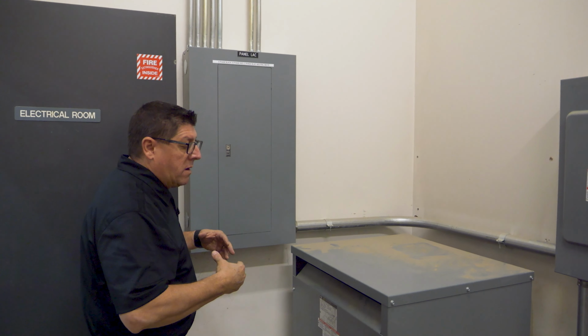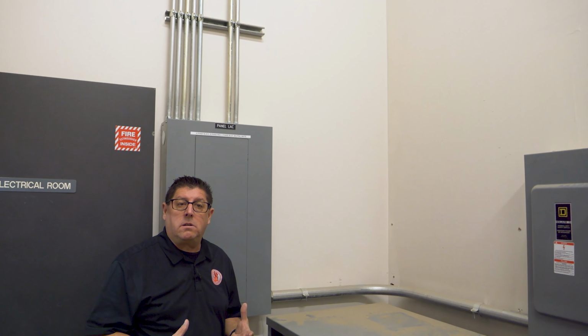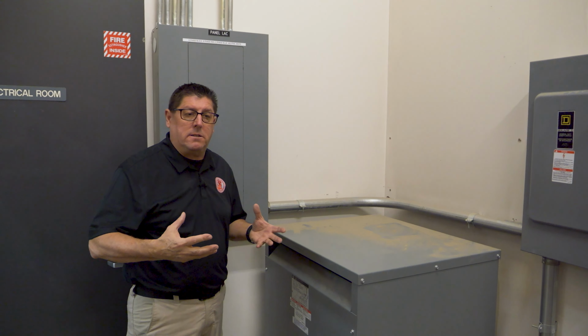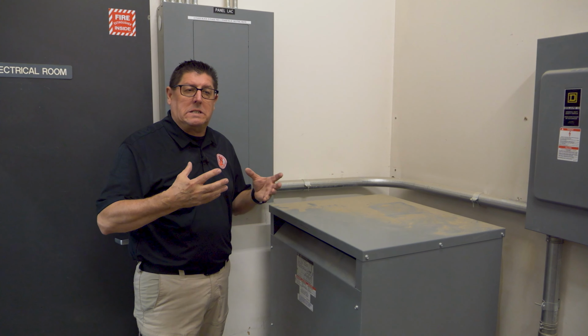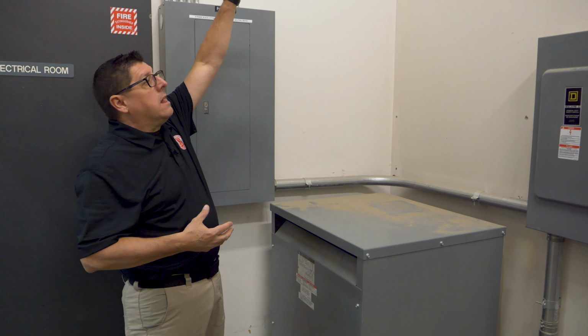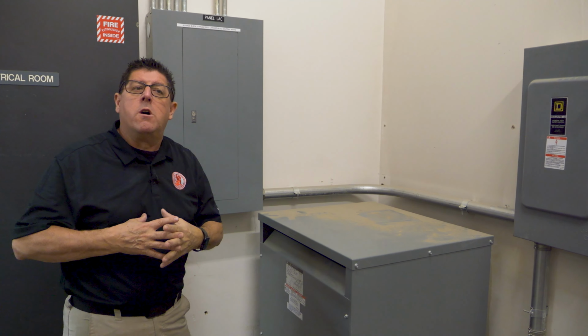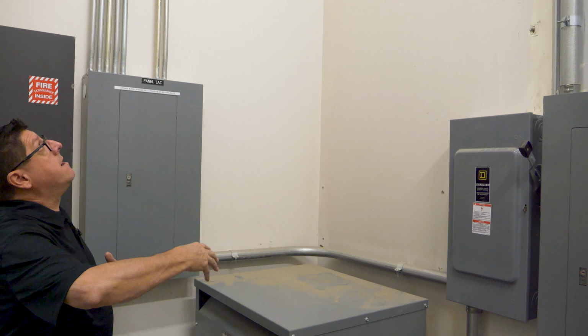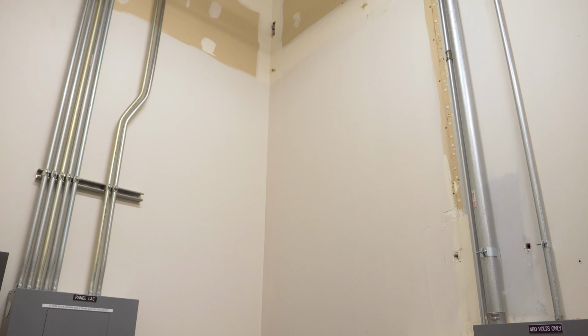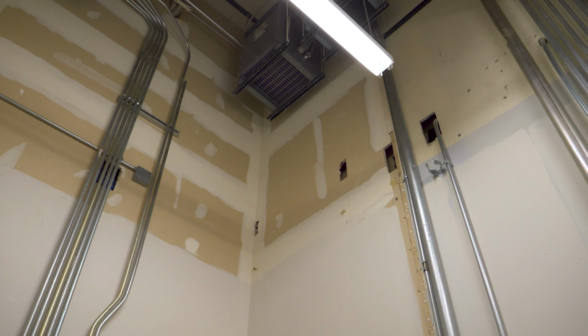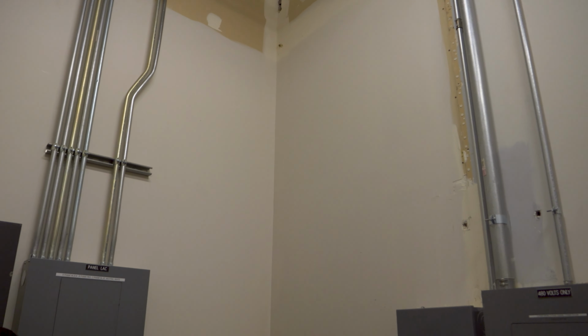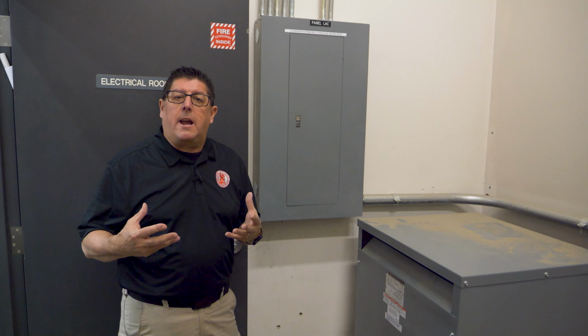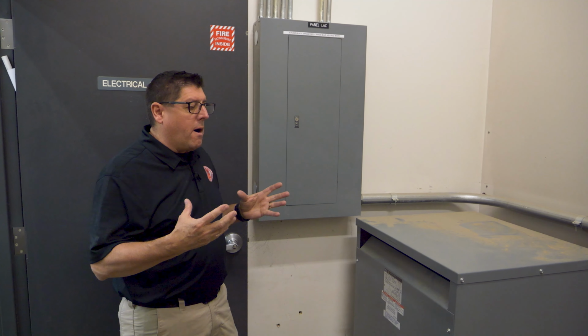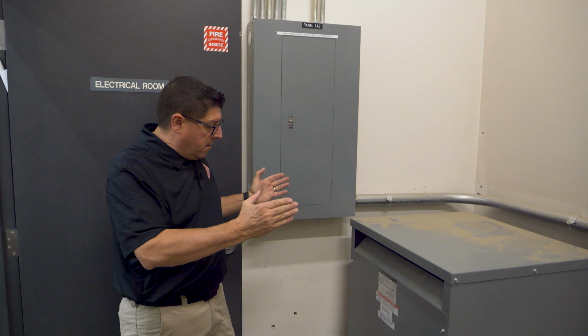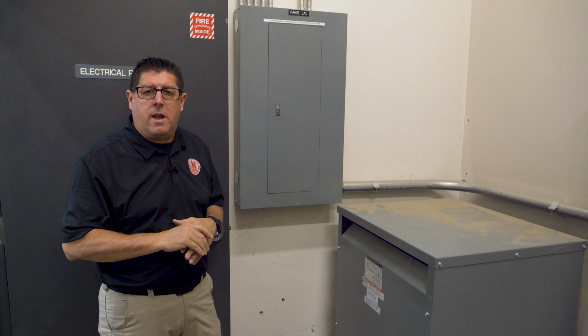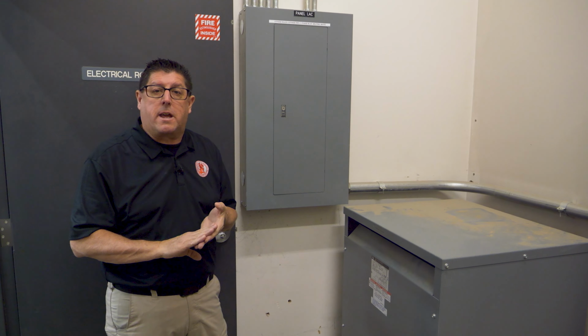Yes. Once I've established my working space, then I can look at dedicated space. And remember, dedicated space extends at least 6 foot up or through the structural ceiling. And in this case, all the way up through the structural ceiling, I do have proper dedicated space. After establishing dedicated working space, I will photograph every transformer. Just the front of the transformer is all that's necessary, unless I had a deficiency in working or dedicated space.